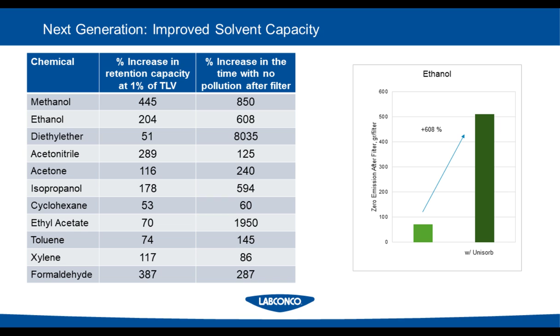So sensors and detection, how is it we go about that 1% TLV exposure that I just talked about? So first off, there's an acid sensor in there, a whole suite of sensors, and a solvent sensor that are both located up in the fan modules. So when that primary filter is no longer at the efficiency that we all want it to be at, we will detect that and we will alarm. Meanwhile, coming back into that laboratory is clean air, no greater than 1% of what you're allowed to be exposed to. So it could be 99% and you'd still be safe. Our guarantee to you is less than 1% of that, just to be extra safe.